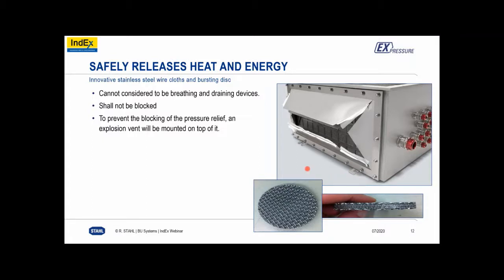Somebody asks, the rupture disc seems thin. Can they handle mechanical hazards such as 7 joules impact protection, as the IP rating depends on them? Now, I believe, Gergely, this enclosure is rated IP66, so it has had also impact testing on it, correct? Yes, yes. Okay. It has more than 7 joules because it's another type of protection. And it's stainless steel, so it is very robust. Okay, let's go to the next slide.